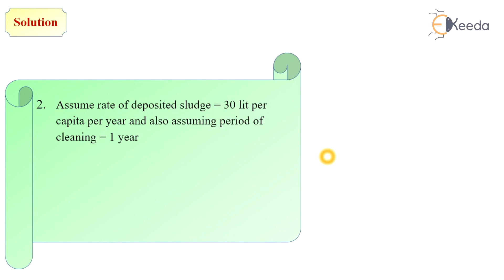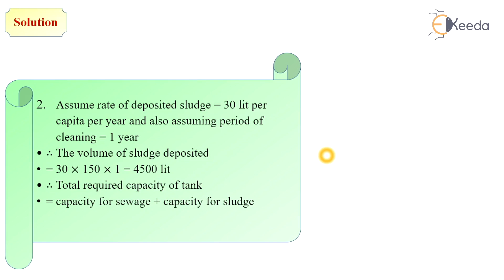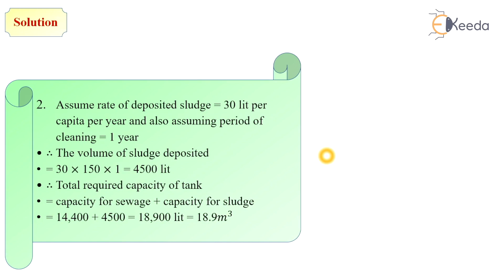Next, assume the rate of deposited sludge equals 30 liters per capita per year, and the period of sludge cleaning is 1 year. The volume of sludge deposited equals 30 into 150 — where 150 is the population — for 1 year, so total sludge deposited is 4,500 liters. The total required capacity of tank is the addition of capacity for flow plus capacity for sludge: 14,400 plus 4,500 equals 18,900 liters.